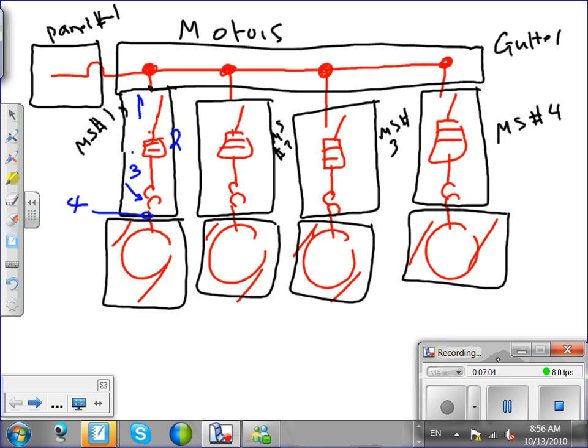So any question is about what we're pointing to. The second thing I'm going to point to is here. Use the same connection. This is number 5, and this one will be number 6. So 6 things I need to calculate. Anybody has any problem with that? Any question? So what is number 5? Number 5 is the feeder that feeds these 4 motors. Number 6 is the overcurrent device that protects these conductors, the main conductors.